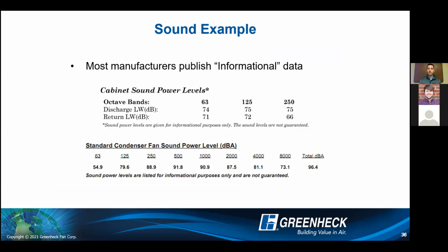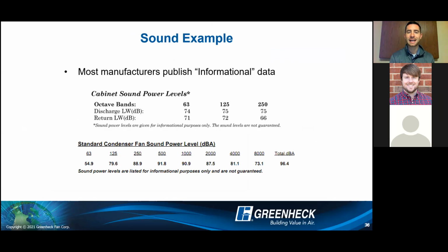An example that you might see from other manufacturers is generally sound power levels are given for informational purposes only, or maybe they're informational and they're not guaranteed. And the concern with that is if you're dealing with a sound tight application, we want to make sure that what we're providing from a sound standpoint gives you the peace of mind that that's how it's going to sound when it's on site. So the radiated sound, we're testing it at full condenser fans, full compressors, full heating, things like that to make sure you know how it's going to operate. We actually had a group out of Boston, Massachusetts, a group of acoustical engineers test our equipment when it was on site, and they tested the same exact information that we had in our submittal. So again, proving that what we're putting out there is accurate, and we do pride ourselves on putting out the most accurate information we can for you guys as the customers.